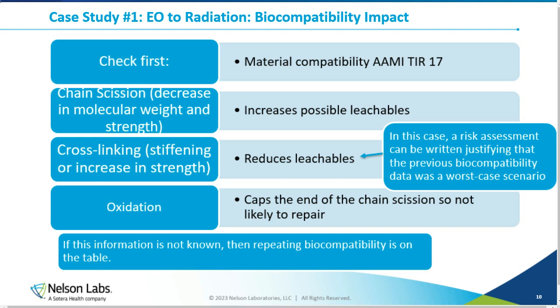With radiation, it's likely we're seeing either chain scission or cross-linking. With chain scission, I use a little mnemonic trick: scission looks like scissors. So the polymer or material chains are actually cut. You decrease your molecular weight and your strength, but you also increase your possible leachables, which is what we care about in biocompatibility, because those studies are based on what's leaching out of the product or device to the patient. If cross-linking occurs, you can have a stiffening or an increase in strength, so we get more of the polymers or molecules crossing together, making a denser matrix, so we don't have as many leachables.